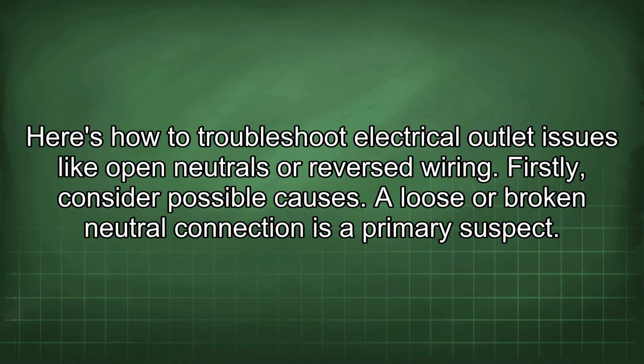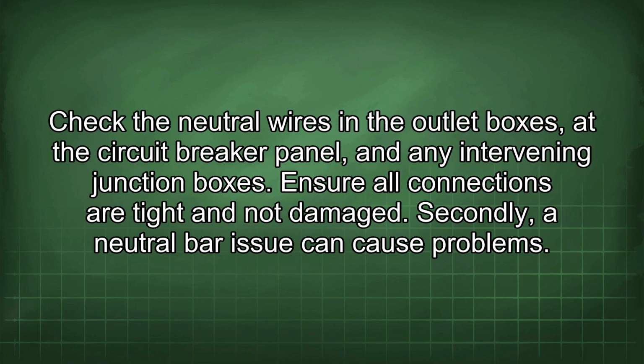Here's how to troubleshoot electrical outlet issues like open neutrals or reverse wiring. Firstly, consider possible causes. A loose or broken neutral connection is a primary suspect. Check the neutral wires in the outlet boxes, at the circuit breaker panel, and any intervening junction boxes. Ensure all connections are tight and not damaged.